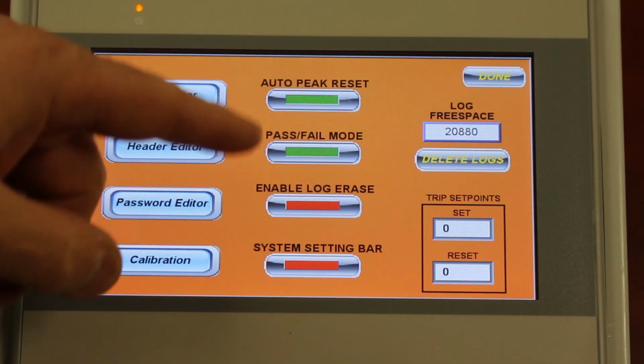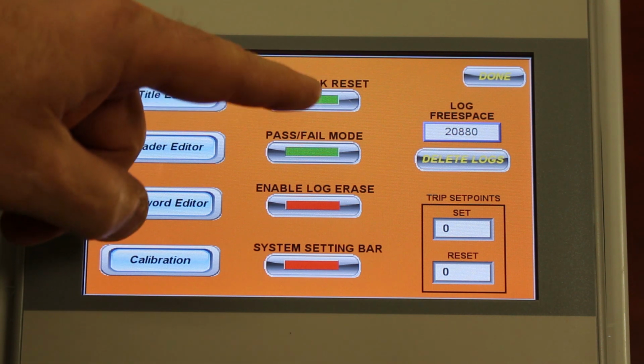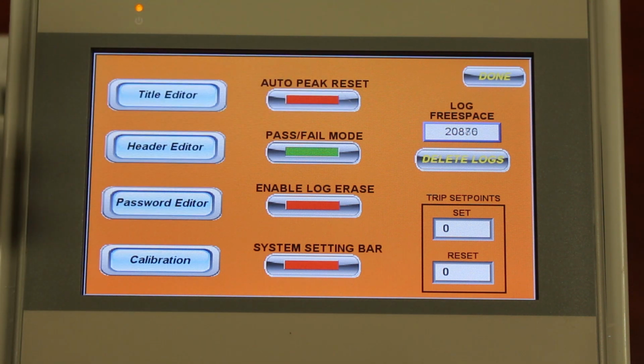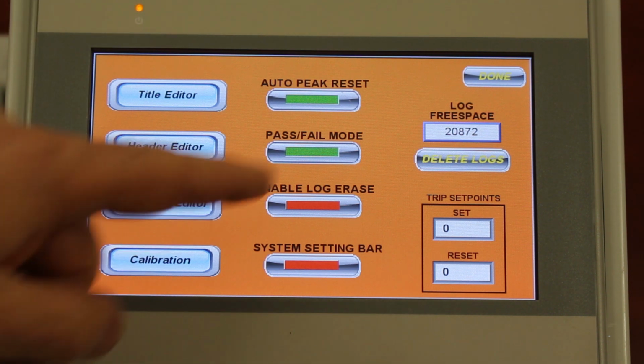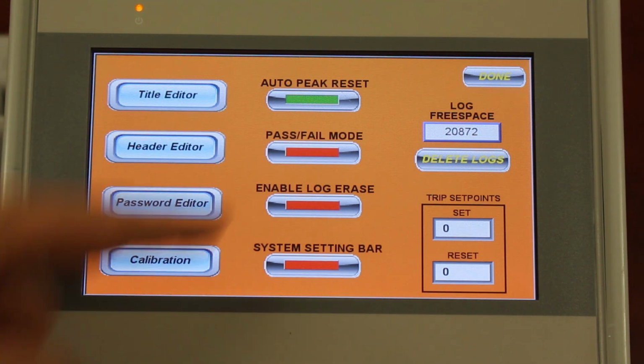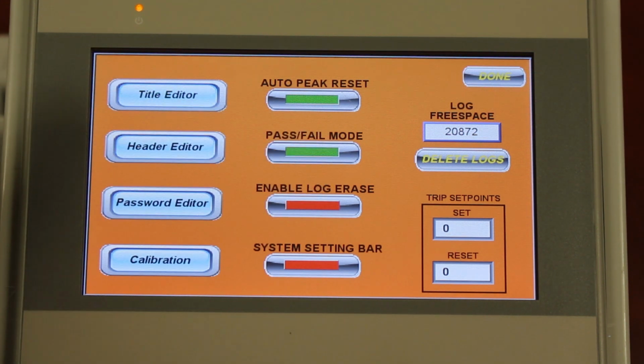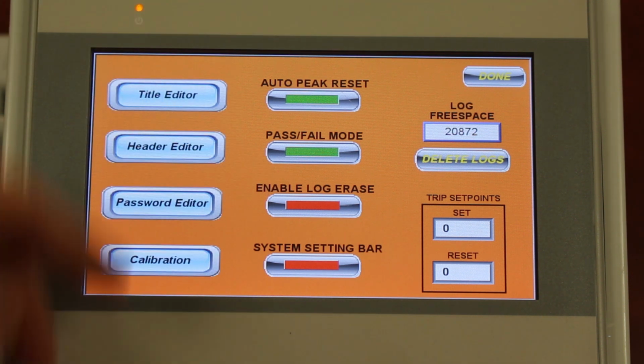There's also some other things you can put in here. There's an auto peak reset, which on the main screen where it has the peak pressure shown, if you have this on, when you finish the test and you're ready to run the next test, it'll automatically zero that back out. You can turn that on or off. There's also a pass or fail. Now what this is on the test report, it'll give you a pass stamp or a fail stamp if you want it to do that. We have it turned on today. You don't have to use that if you don't want to. And some other things for erasing the logs.